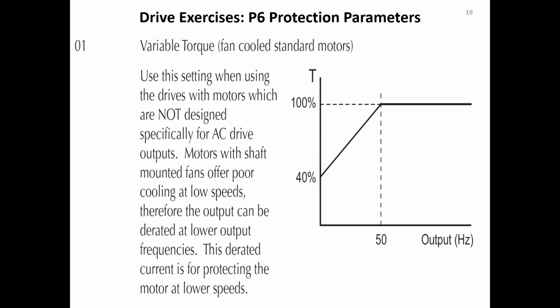One of the things I might add also is that we mentioned earlier that if you do use a non-inverter type motor, you'll have to select this particular address. So they recognize the fact, and let's read through that. When using this setting with drives that are not designed specifically for drives, motor and shaft fans provide poor cooling. So they know that. And I think I said 50% speed. They say 40%. I try not to run it down that slow, but you can, 40%, but I keep it 50%. No need to test the cooling of these things.